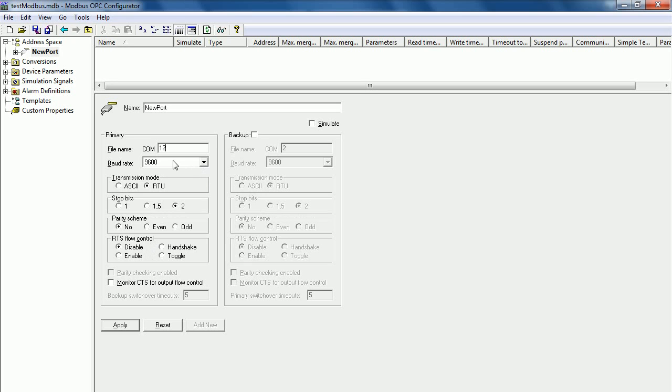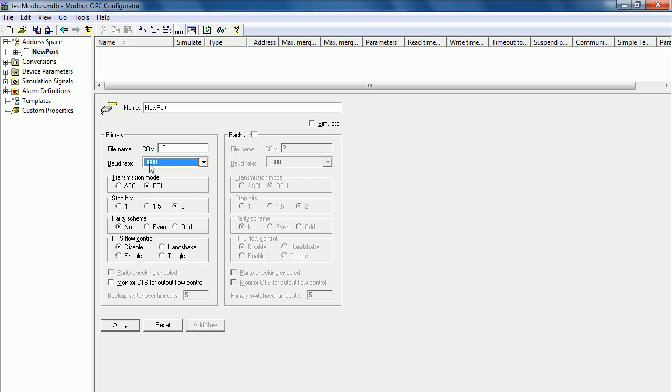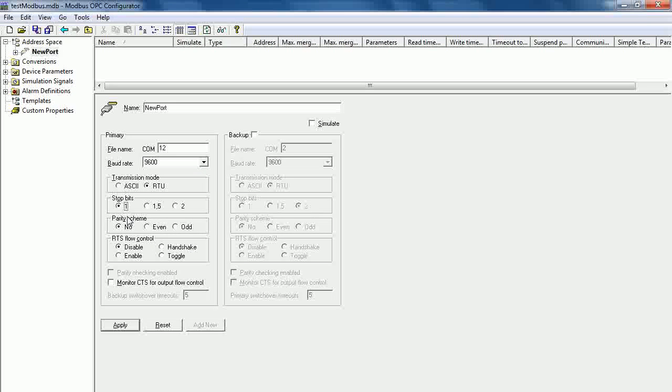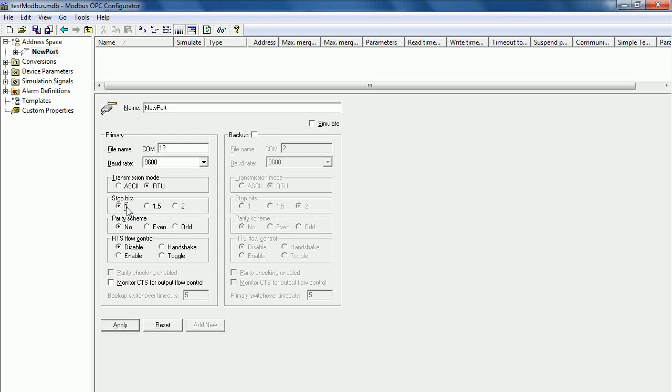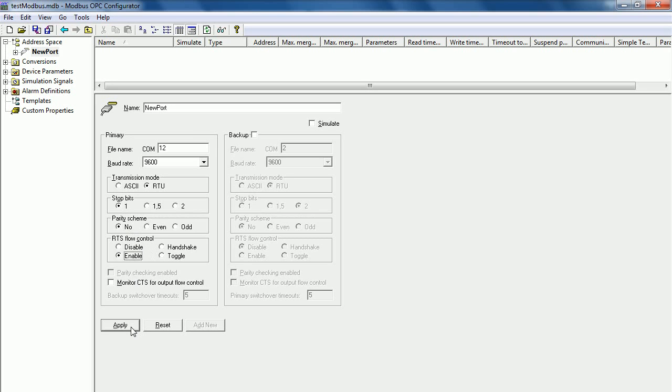In this example, I use the baud rate at 9600 and the RTU mode, stop bit is 1, and parity is none. Now, RTS flow control is enabled. And then click Apply.